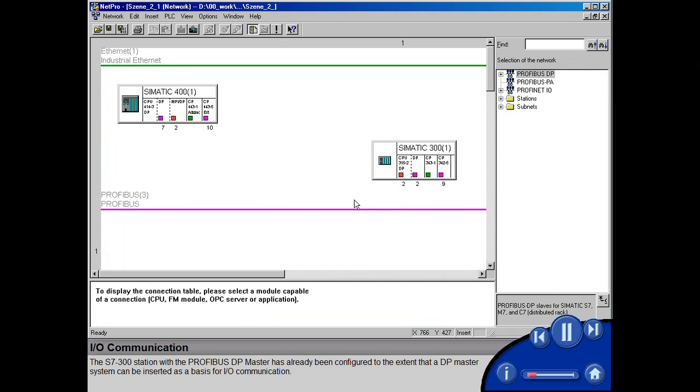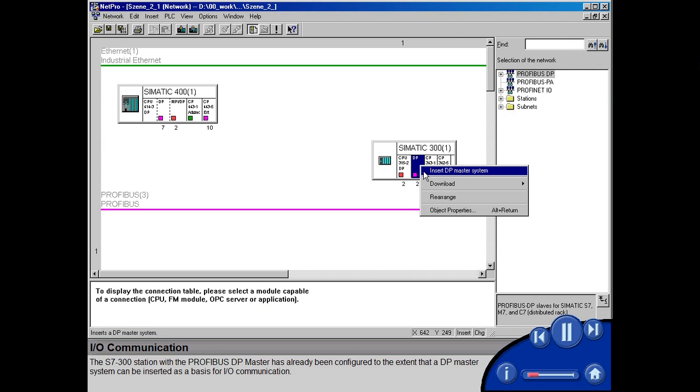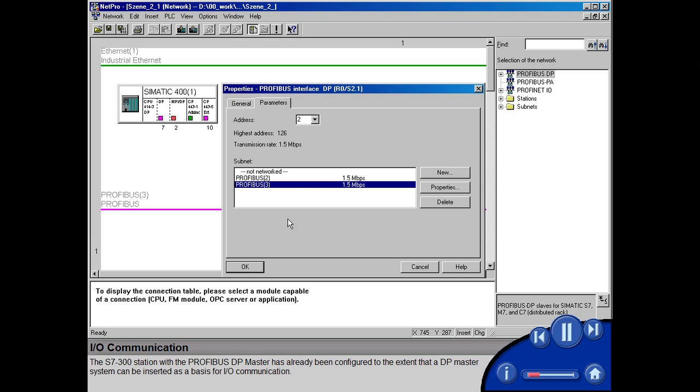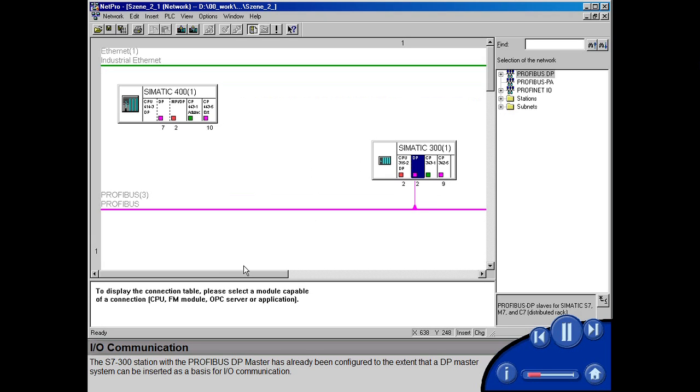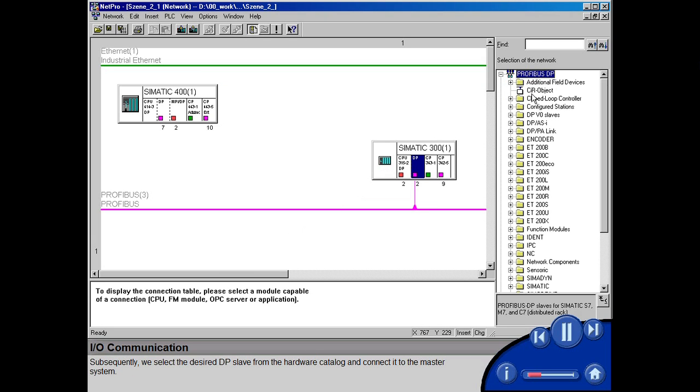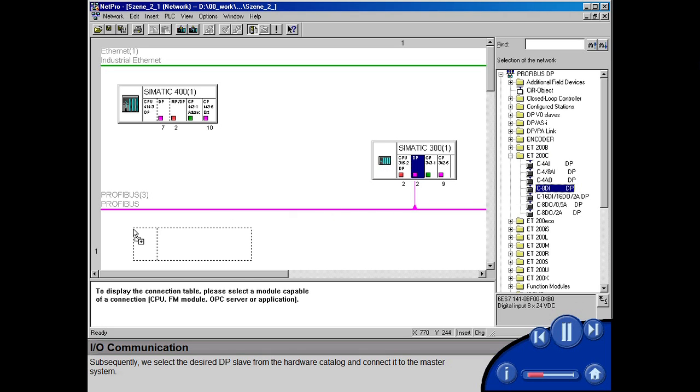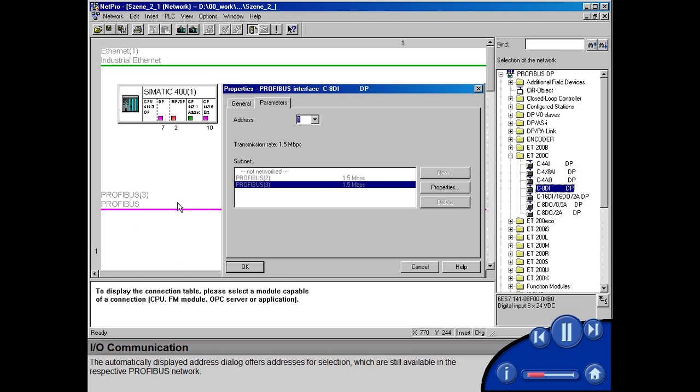The S7-300 station with the PROFIBUS DP master has already been configured to the extent that a DP master system can be inserted as a basis for I/O communication. Subsequently, we select the desired DP slave from the hardware catalog and connect it to the master system. The automatically displayed address dialog offers addresses for selection, which are still available in the respective PROFIBUS network.